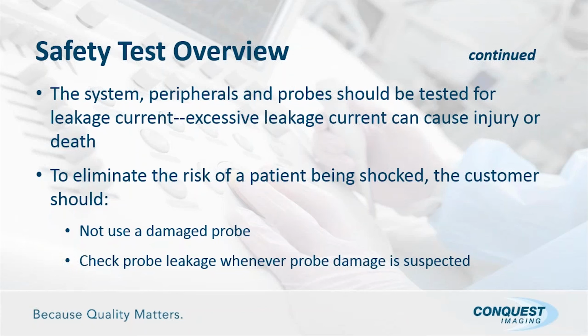To eliminate the risk of the patient being shocked, the customer should, well, you shouldn't use a damaged probe. What's a damaged probe? It's a probe where the lens is partially missing or the casing's cracked. If you have the ability to test a probe for electrical safety, please do. But even if it passes electrical safety, if it is clearly damaged, it should be removed from service. And you need to check the probe leakage whenever damage is suspected. But again, I want to clarify that this is no time to leave the probe in service. If you can see it's damaged, whether it passes electrical safety or not, we should remove it from service and get it repaired.